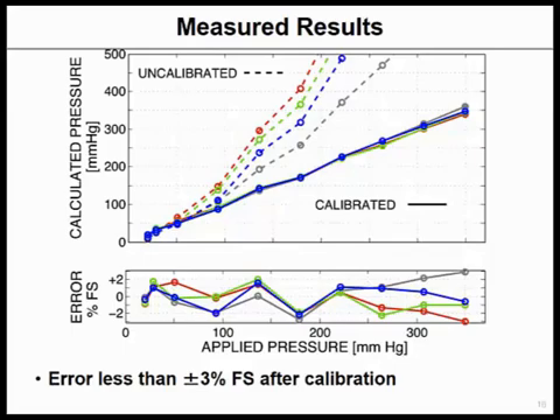You can see looking at the deviation from linearity, we're within plus or minus 3% of full scale. And we're using a 2-point calibration at minimum and then at about 2/3 full scale. And the calibration procedure is also implemented in the microcontroller. So when we set it up, we just apply these two known forces, and it'll calculate the parameters to use.